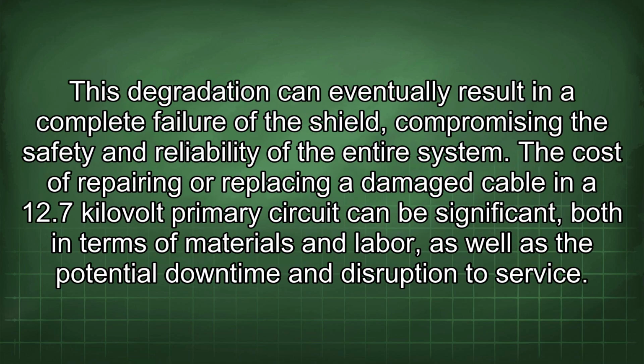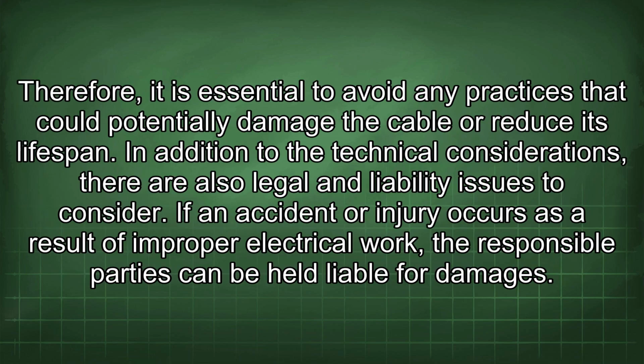This degradation can eventually result in a complete failure of the shield, compromising the safety and reliability of the entire system. The cost of repairing or replacing a damaged cable in a 12.7 kilovolt primary circuit can be significant, both in terms of materials and labor, as well as the potential downtime and disruption to service. Therefore, it is essential to avoid any practices that could potentially damage the cable or reduce its lifespan.